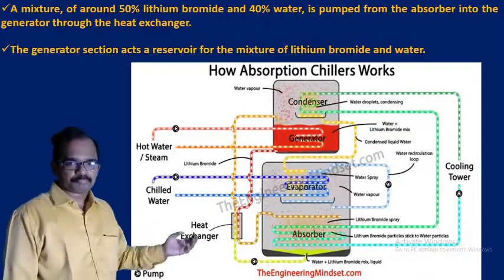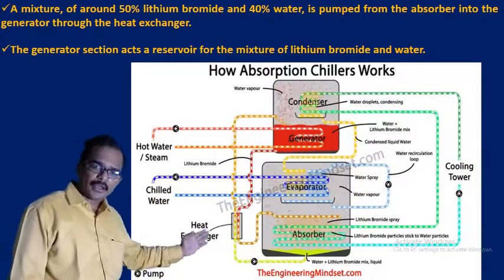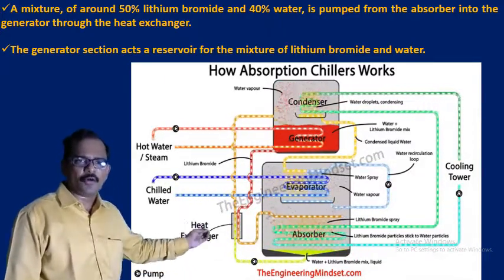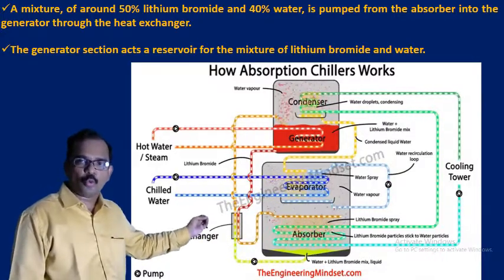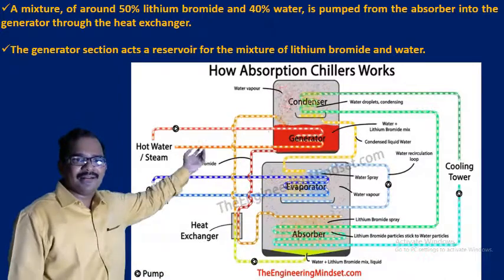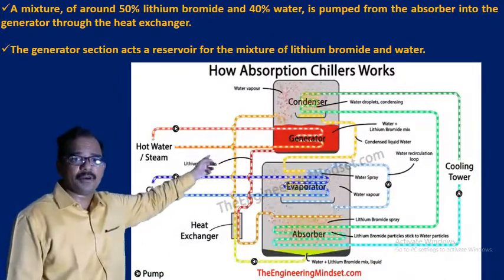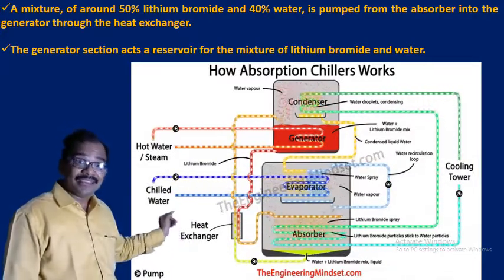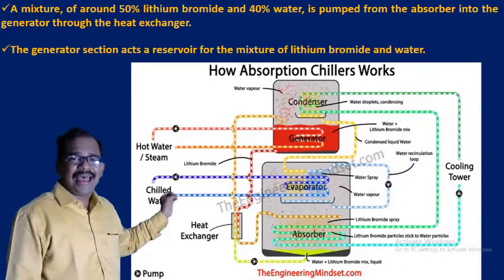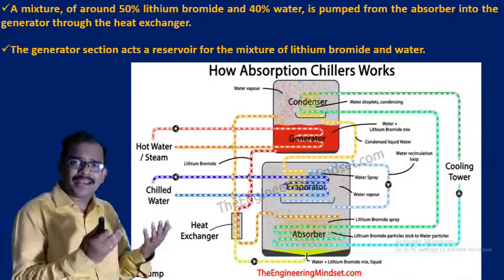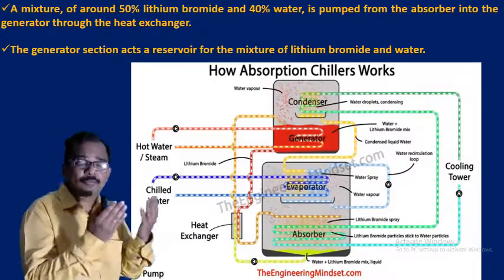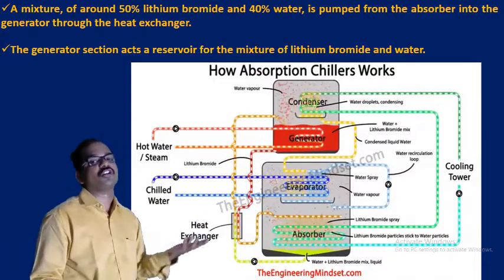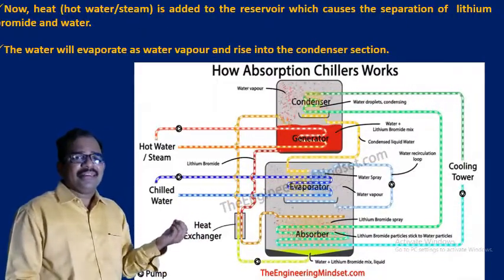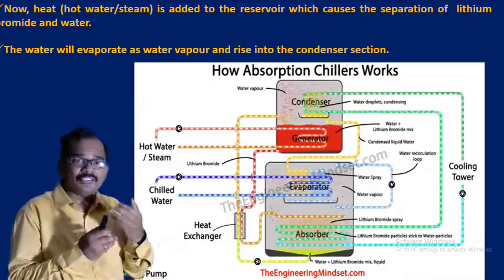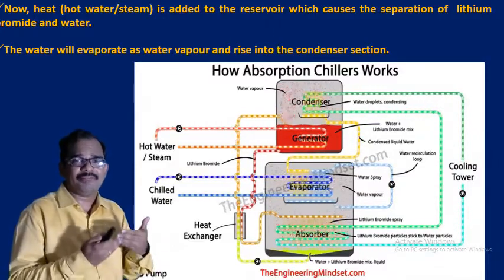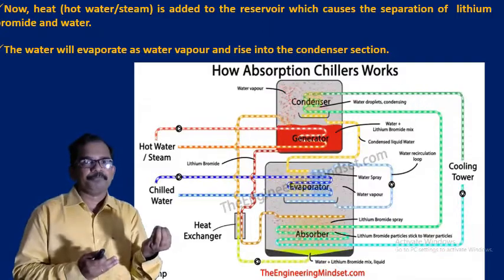Right? Initially, as you can see here, the operation starts at the absorber. In the absorber, a mixture of around 50% lithium bromide and 40% water is pumped from the absorber into the generator, which is located in the topmost chamber, through a heat exchanger. This generator section acts as a reservoir for the mixture of lithium bromide and water. So the generator is otherwise called a reservoir of the lithium bromide and water solution. So now, heat in the form of hot water or steam is added to the generator or reservoir where the mixture of lithium bromide and water exists.